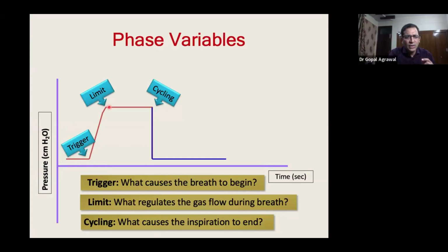Limit is what causes the gas flow regulation during inspiration. So the variable which regulates the gas flow during inspiration is the limit. Cycling is the variable which decides when the inspiration ends and when the expiration starts. So cycling from inspiration to expiration is cycling. So trigger, limit, and cycling. These three variables are very important to understand the basic concepts of various modes of ventilation.